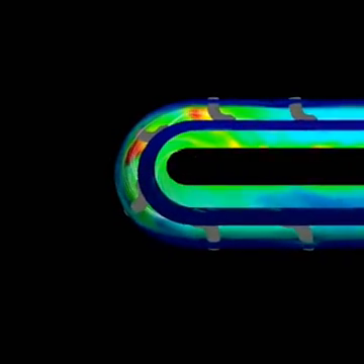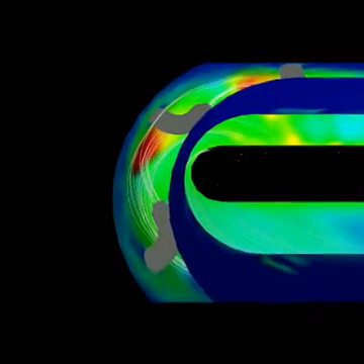What we see here is the top of part of a Venturi scrubber used to remove particulates emitted from a cementing plant. An inner wall was placed to form an annular flow channel in order to eliminate erosion.